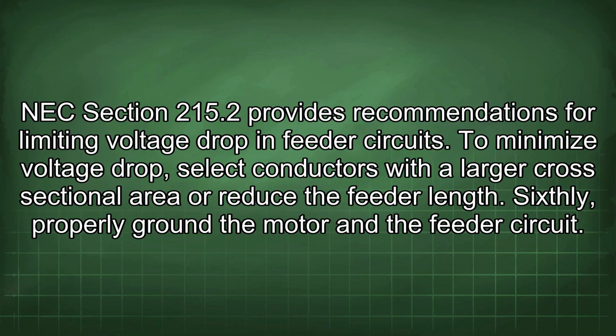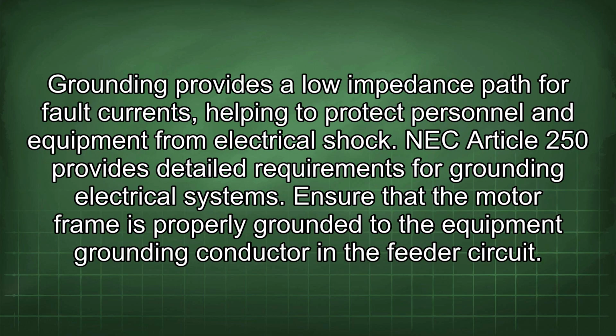Sixthly, properly ground the motor and the feeder circuit. Grounding provides a low impedance path for fault currents, helping to protect personnel and equipment from electrical shock. NEC Article 250 provides detailed requirements for grounding electrical systems. Ensure that the motor frame is properly grounded to the equipment grounding conductor in the feeder circuit.